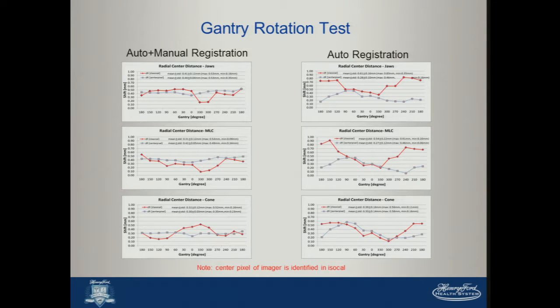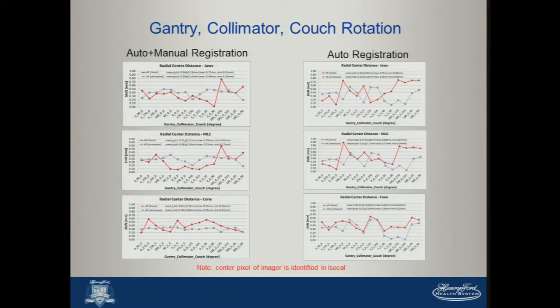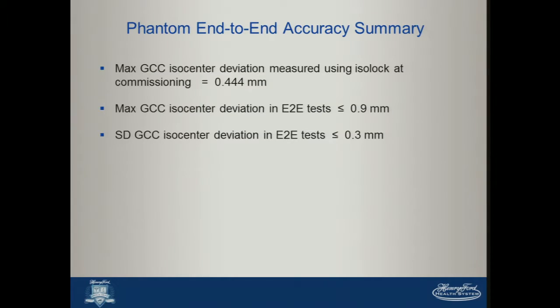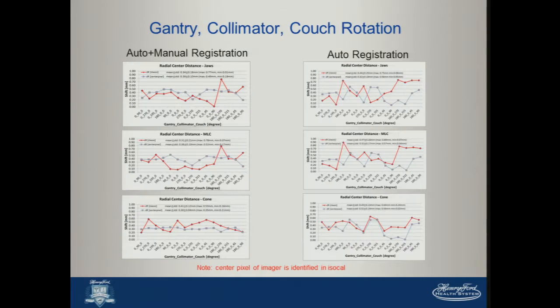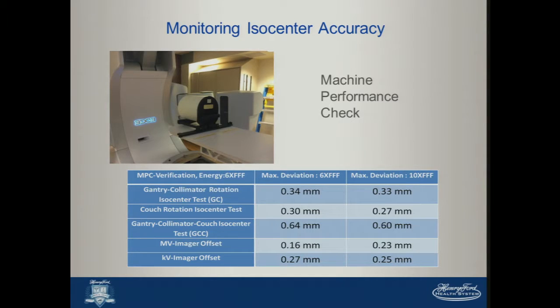So we didn't trust these systems, of course. We did our own verifications. There are some kind of busy plots that I got from Winston, but they show that we use the IsoCal system to measure the offset of the center of jaw-defined, MLC-defined, and cone-defined fields from the nominal isocenter position, over different gantry and couch rotation angles, and using either auto registration that's built into IsoCal or auto with manual corrections, and basically verified that the numbers we get out of this exercise closely match what we get out of the machine performance check software.